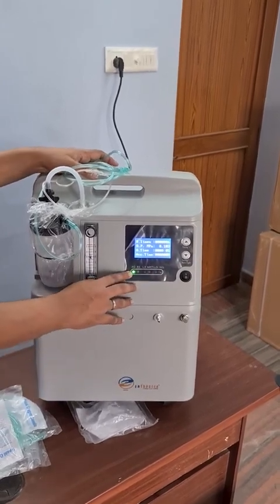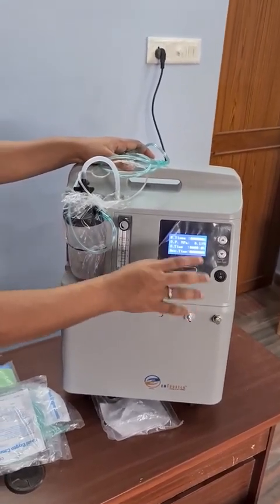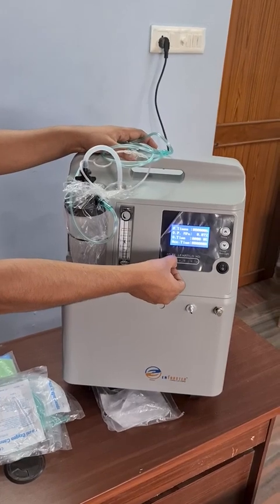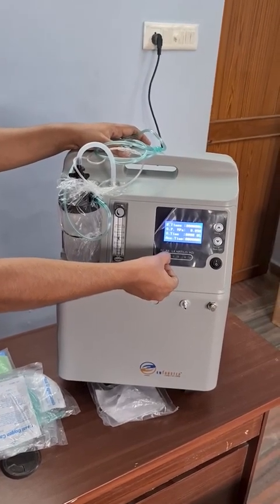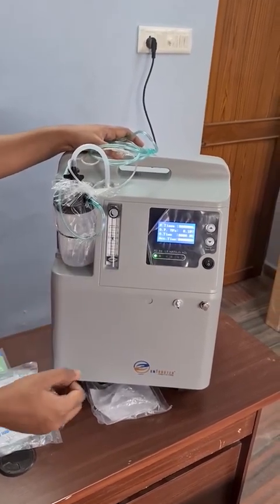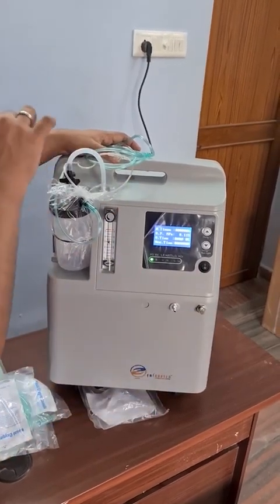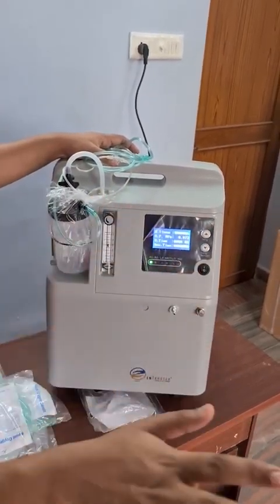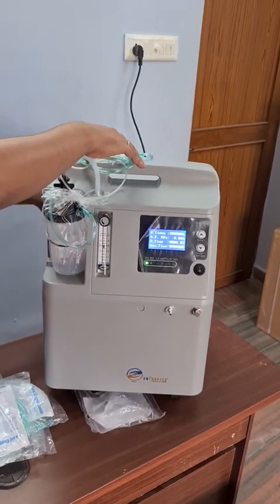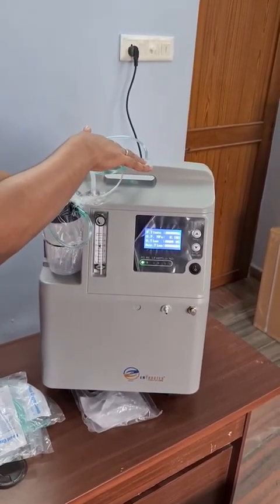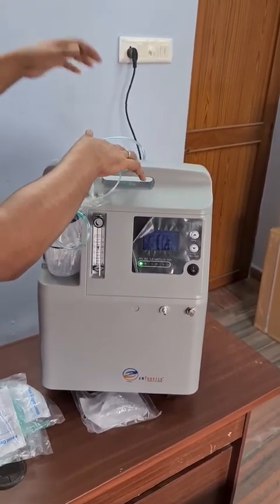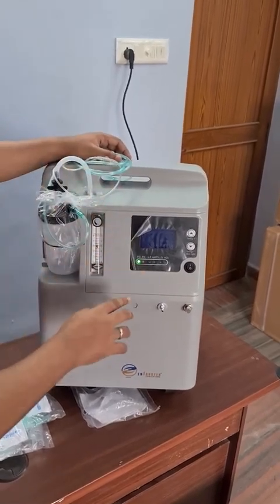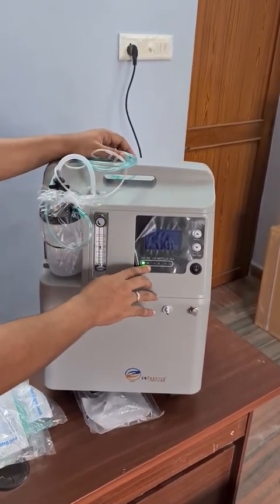Now coming on to the alarms, this is power on, and in case the power fails, you will get a red color light here, which means power failure. Power failure will happen only in two cases. Either your electrical supply is off, or otherwise you have disconnected the power cord at the backside of the device, or you have not placed it properly, or maybe there is a disconnection in your main board. So that is the only time you are going to get the power failure.